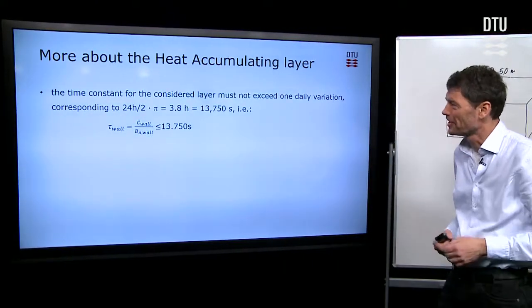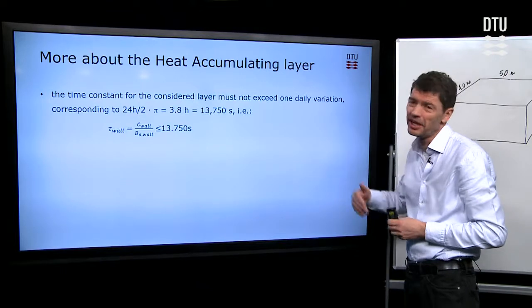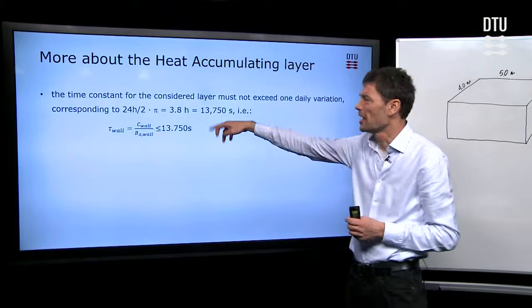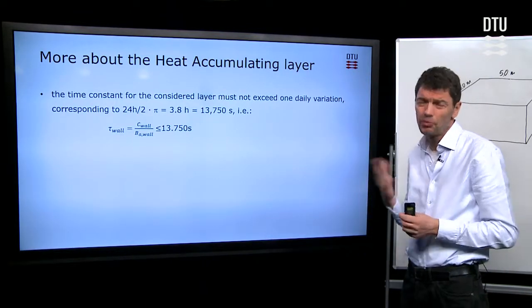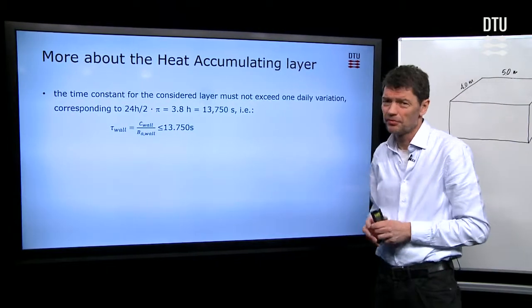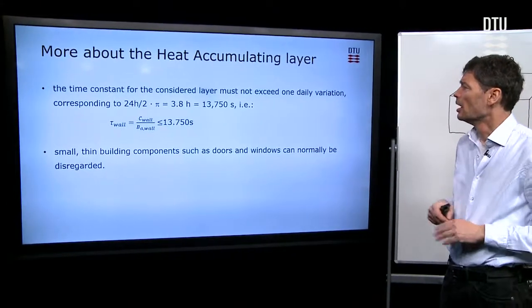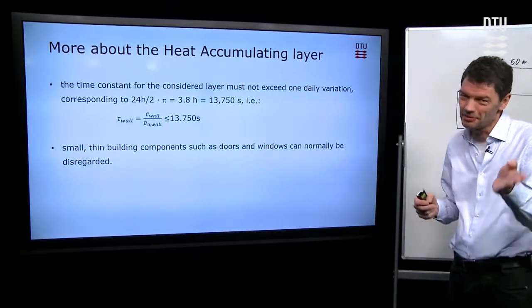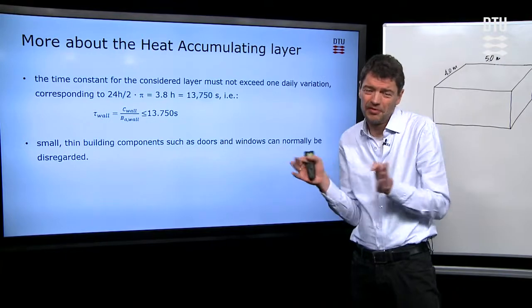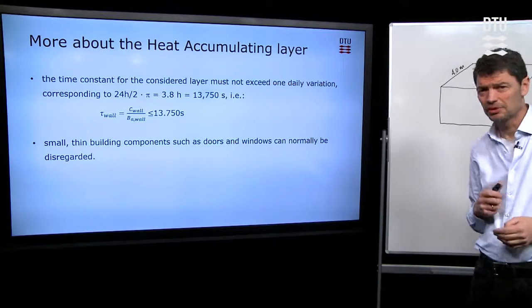And finally, two more things here. The first one, the time constant for the layer that we consider should not exceed one daily variation if we're talking, as I said before, normally about daily variations. And when we calculate that, it corresponds to having a time constant with the definition I introduced before about the percentages. It's around 13 to 14,000 seconds that you should consider at most. And then finally, you can also ask, I said furniture. You can also ask what about doors, windows, and so forth. But if things become very small, simply neglect them. They might not be important in contributing to heat capacity for the room.